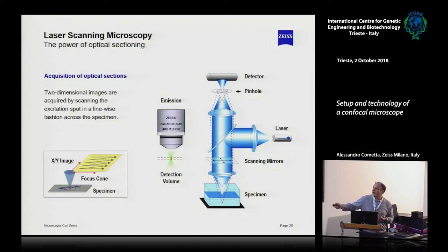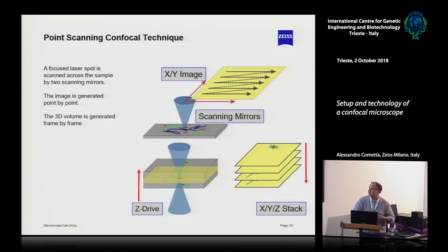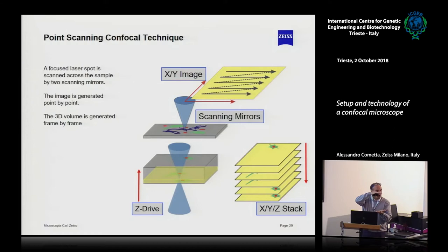However, I just have a point, because from the pinhole I filter everything but the point. So I need to acquire point by point a line, and line by line to create the image. So the confocal is usually a very slow instrument. The idea is to acquire plane by plane.